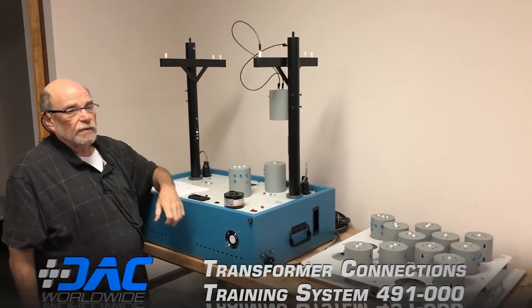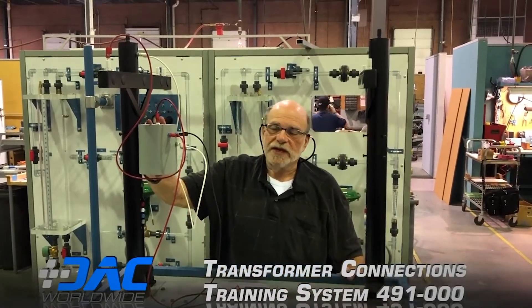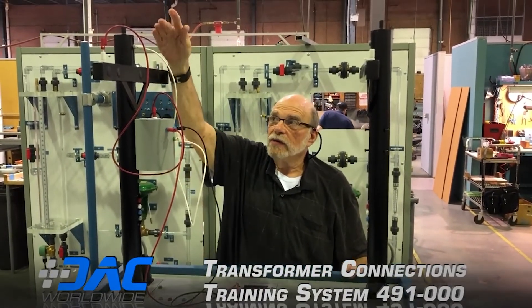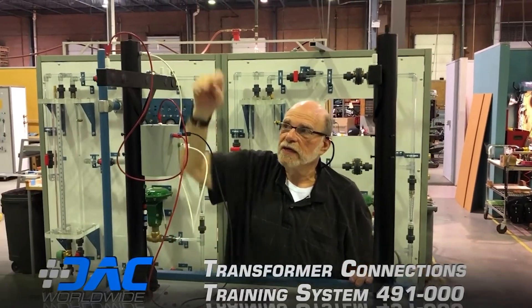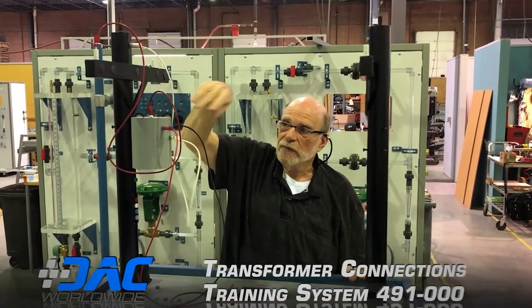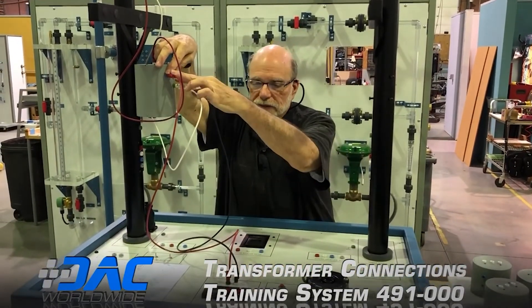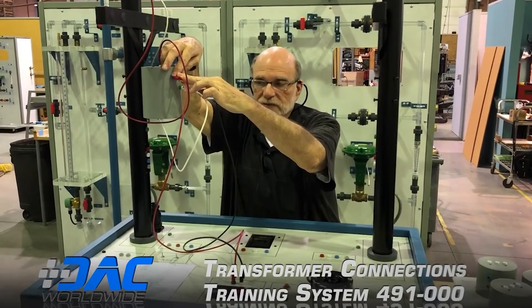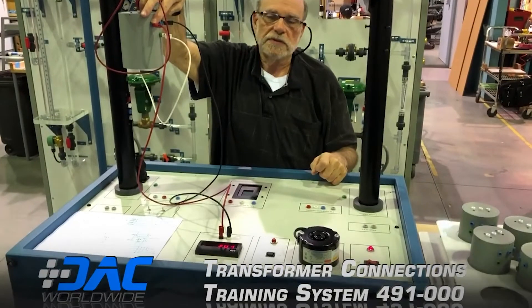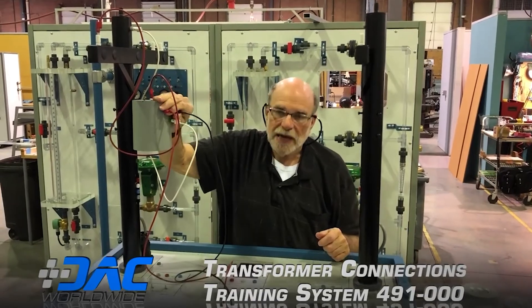We have set up one of the single phase transformers on pole number one. We're feeding it with neutral into the green connection and phase A into the transformer input. On the output, the meter is connected to the two outer terminals of the service entrance, and we're reading approximately 240 volts. Moving the meter connection to the center tap gives us a reading of about 120 volts.